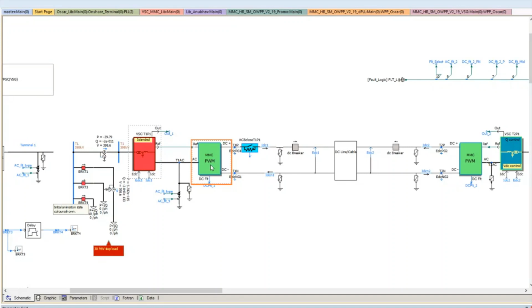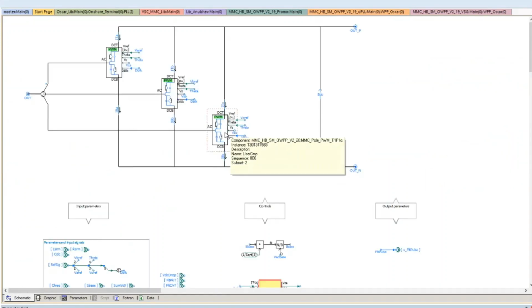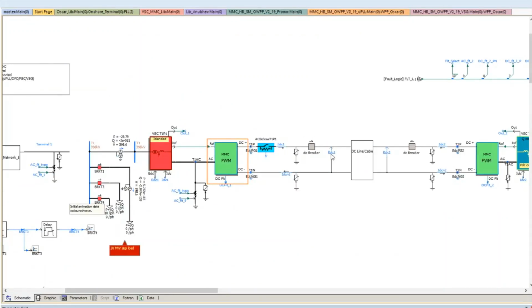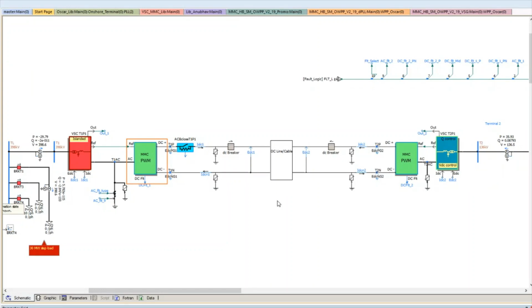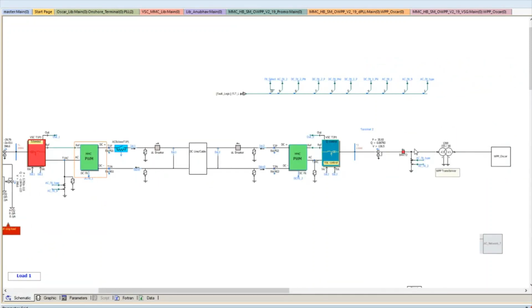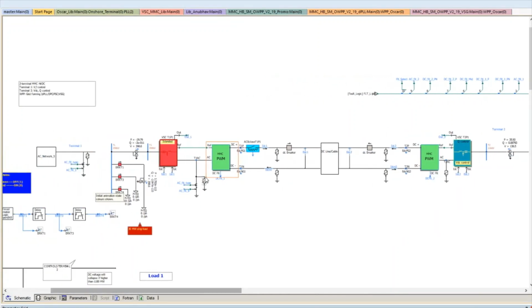However, there's a difference in the onshore MMC model because of the pre-charging during the energization, which I will show in a bit when I show the energization sequence. From the offshore side, the wind power plant energizes the offshore transformer and the MMC cells. So the offshore MMC charges from the AC side, and then starts to control the DC link voltage. Then the onshore MMC is pre-charged from the DC side. Due to this difference, some extra controlled pre-charging is required to avoid significant transients over the HVDC link, due to the energy oscillation between the offshore cells and the onshore cells.